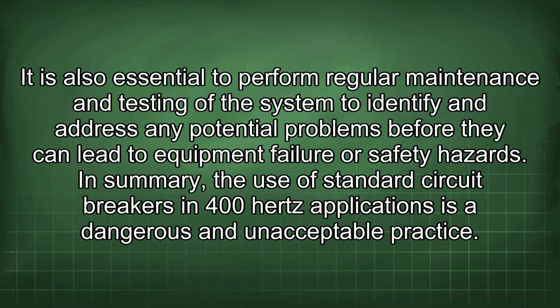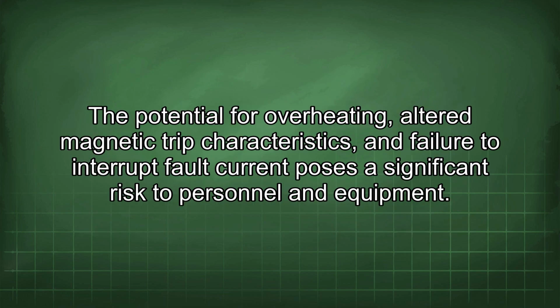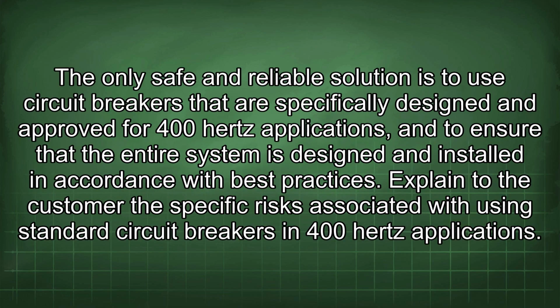In summary, the use of standard circuit breakers in 400 Hz applications is a dangerous and unacceptable practice. The potential for overheating, altered magnetic trip characteristics, and failure to interrupt fault current poses a significant risk to personnel and equipment. The only safe and reliable solution is to use circuit breakers that are specifically designed and approved for 400 Hz applications, and to ensure that the entire system is designed and installed in accordance with best practices.